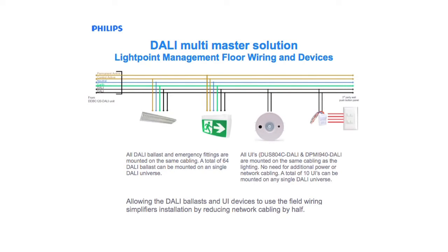The DALI emergency fittings and the DALI ballast both consume DALI addresses. A total of 64 of these devices can be put onto a single network. Some DALI emergency fittings consume 2 addresses, and it is highly recommendable that you investigate its requirements. It's also recommended that a DALI universe is not loaded to its full 64 capacity. Some spare capacity should always be left within a DALI network.